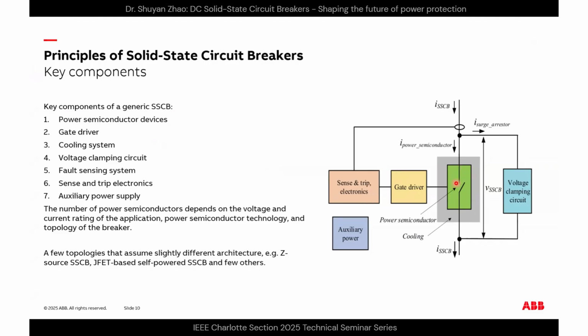First, of course, most important are the main power semiconductor devices that work as the main switch here. And the gate driver of this semiconductor device, and also its cooling system. And then the voltage clamping circuit in parallel with the main branch, the main topology. And number 5 is the fault sensing system, which consists of sensing and trip electronics. And the last is the auxiliary power supply, which provides power to all the active components in this architecture here.